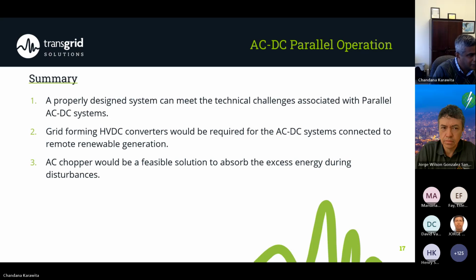Yeah, it would be quite challenging, especially the lightning would be very similar, because if it is an overhead system, we have to consider lightning strikes on both AC and DC. And again, we may have to consider backflashover issues and so on. So there are added challenges with insulation coordination when you have AC and DC on the same corridor. Another concern I quickly mentioned is transient overvoltages because of the faults on the other system. So this will affect the insulation coordination as well, especially switching studies.